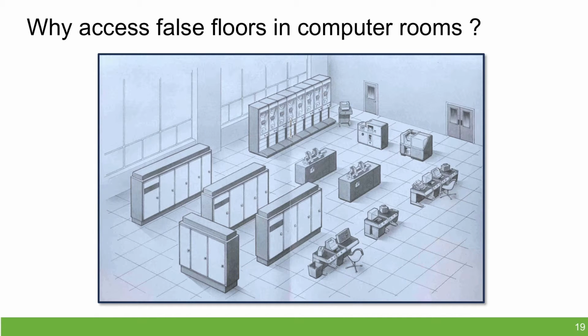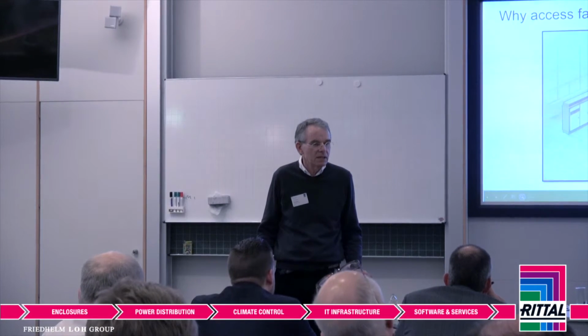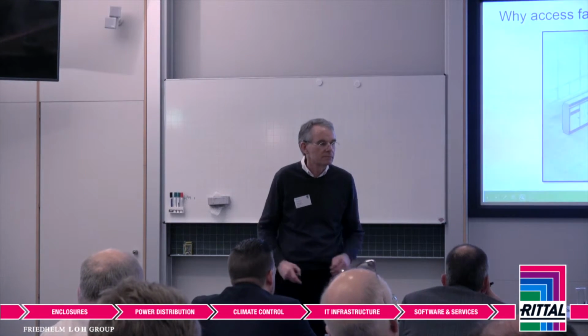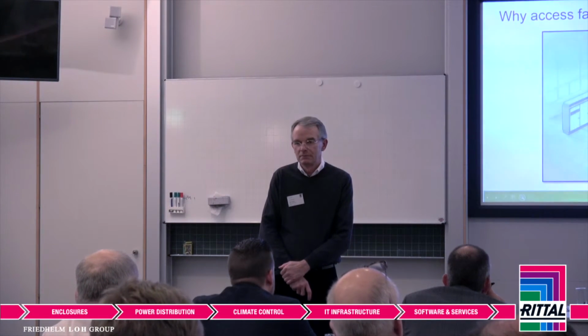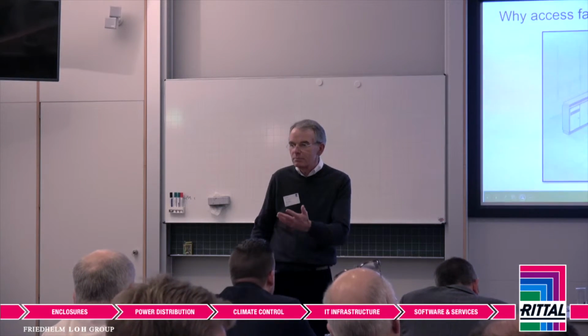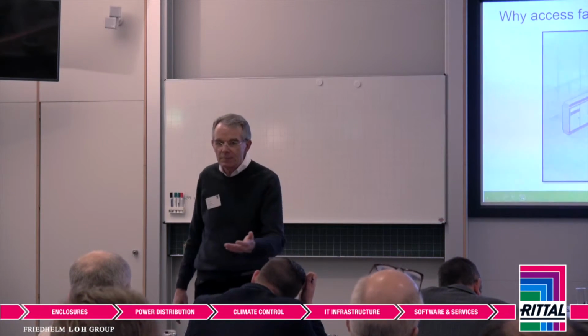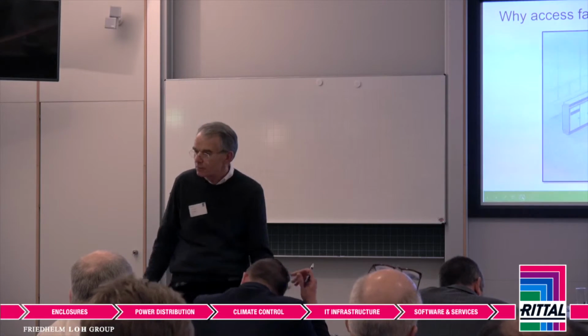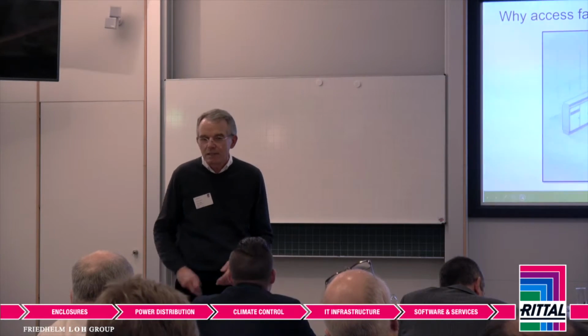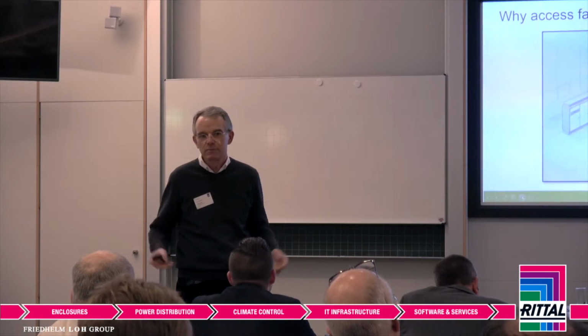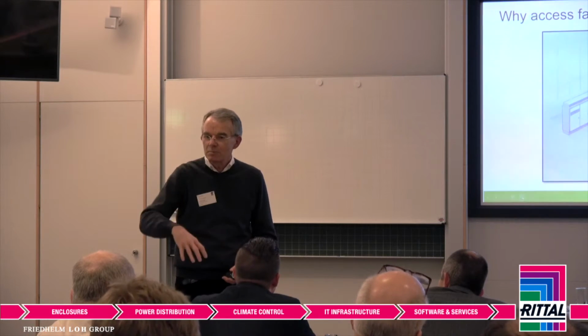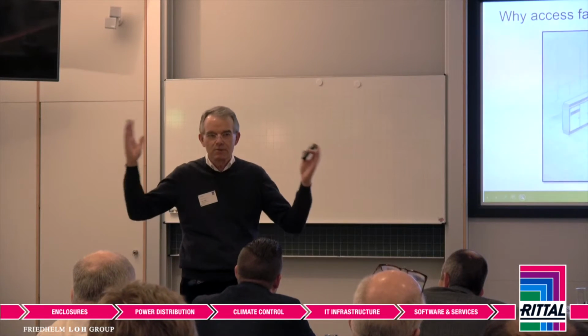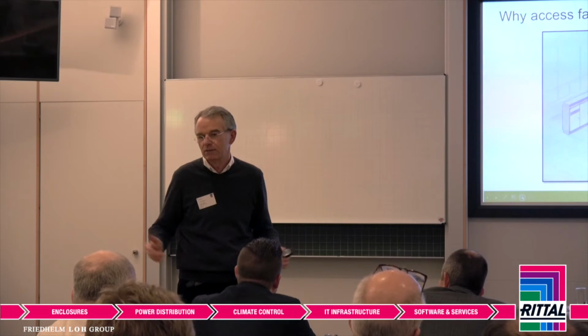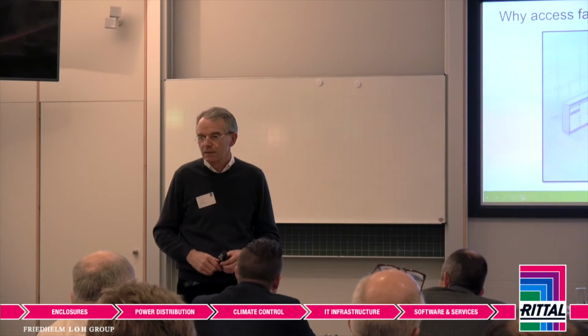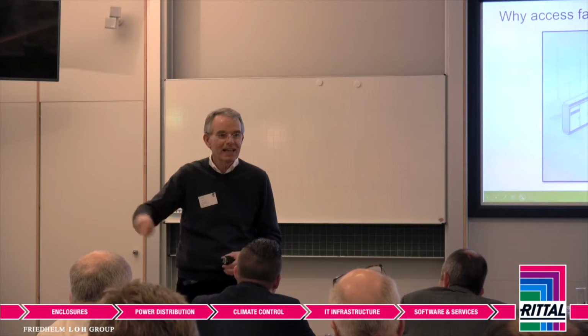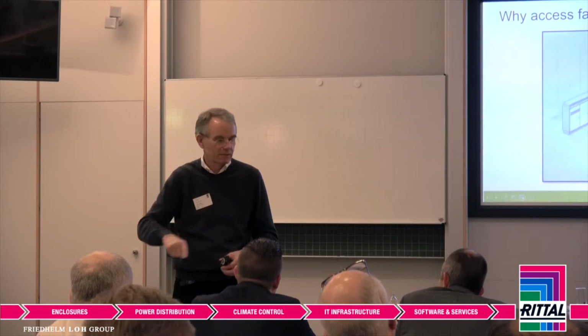You put water pipes under the floor because if there's a leak, you don't damage the mainframe. Then when air-cooled servers came in, people started pumping air under the floor and pushing it up through vented tiles. It's the most stupid way to vent the room. You pour cold air into the warm space and it's denser, so it just falls on its own. You don't really need any fan power. You can create a kind of rotating stack effect, so it's almost passive.